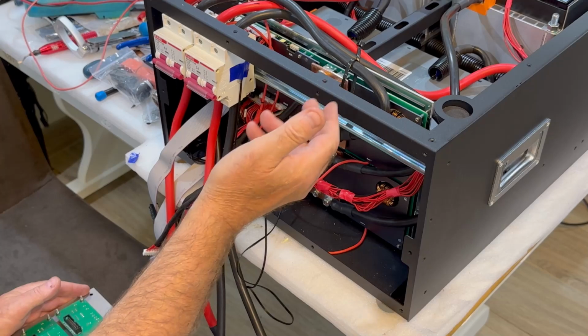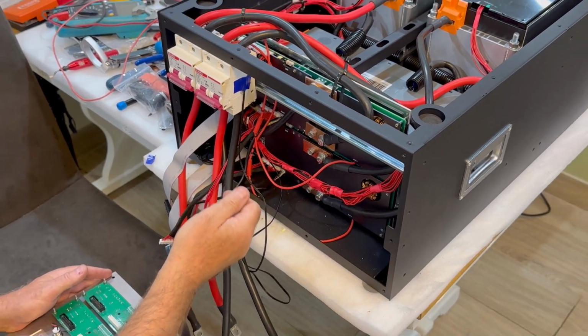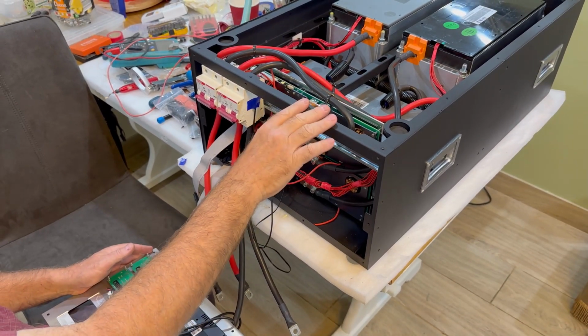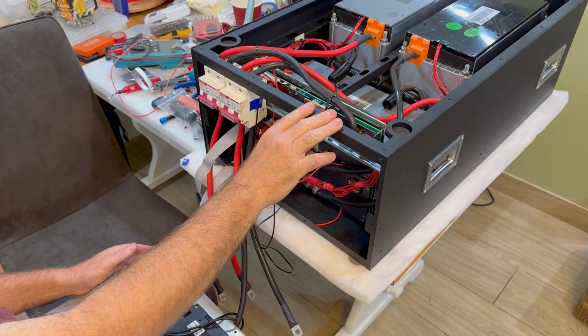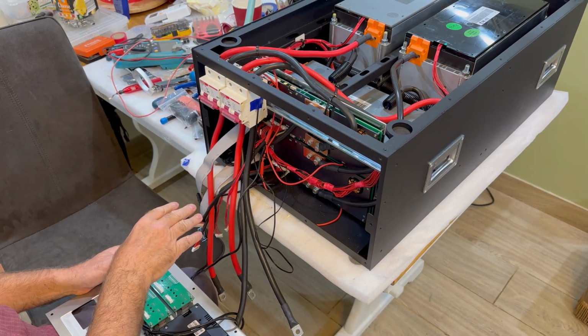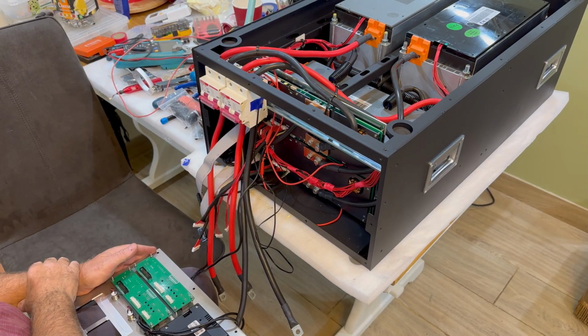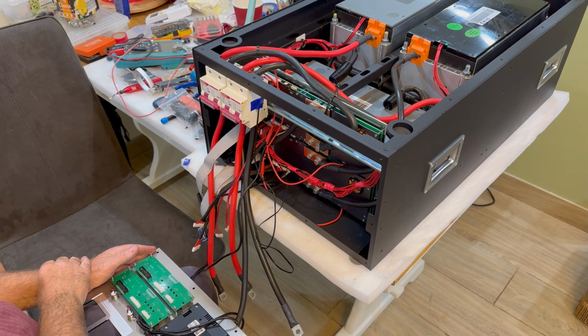But for volt drop, the bigger the cable, the less volt drop there is. In DC, especially at 48 volts and lower voltages, the volt drop is the killer - it's what takes away your efficiencies. So the bigger cable you can go, the better.